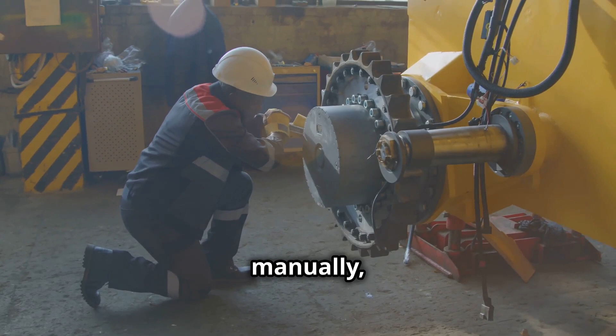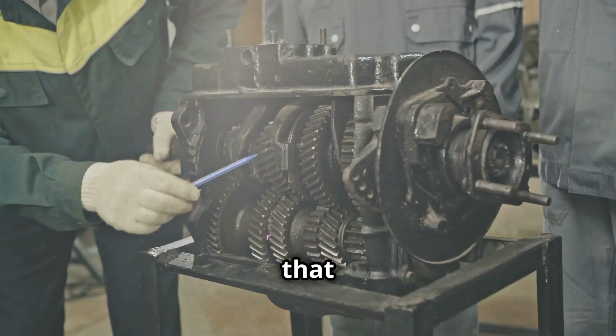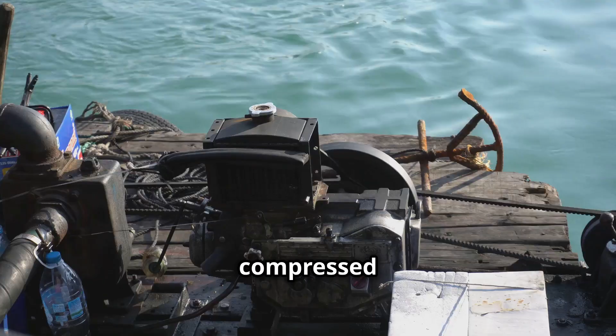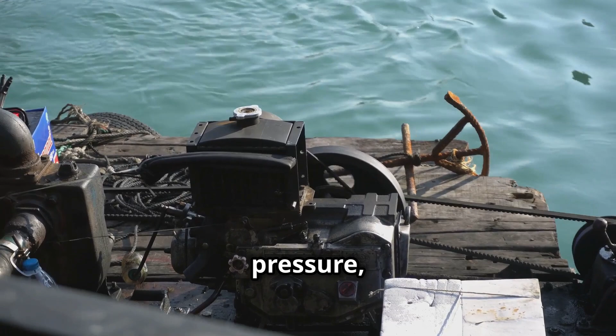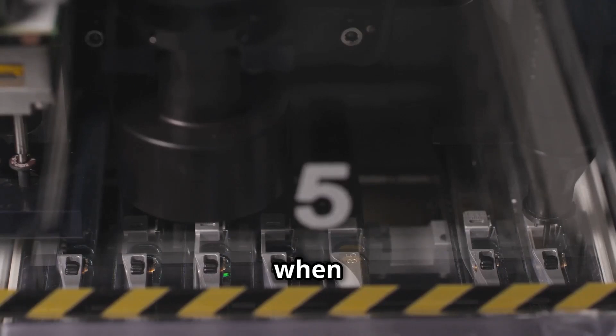Mechanical systems can be verified by attempting to operate the equipment manually, ensuring that all moving parts are stationary and that no stored energy, such as compressed springs or hydraulic pressure, remains in the system. Use extreme caution when performing this step, as even a small amount of stored energy can cause serious injury.